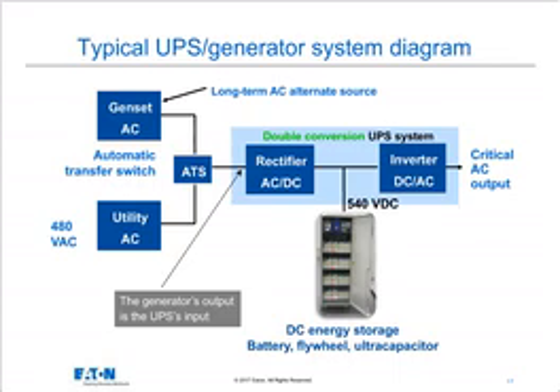So the next slide here shows the typical layout that I'm sure most of you are familiar with, where the generator feeds the UPS. And you can see a little block diagram here with the utility incoming power and the generator. The ATS is the automatic transfer switch. And then we're feeding one of the two sources, either the genset or the utility, into the UPS input. And the automatic transfer switch will typically have a set of auxiliary contacts that communicate its status to the UPS. So what that means is the UPS will know if it's being fed by utility power or by generator power.